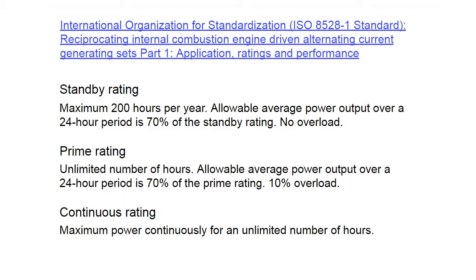As far as the different ratings, I saw some questions about different ratings of systems. So the ISO has ratings and performance requirements. Basically, a standby engine, by their standards, is a maximum of 200 hours a year. The allowable average output over a 24-hour period is 70% of its rating, and it does not have overload. So with a data center, where you'll see engines that may have to run for weeks because it's trying to maintain the system during the whole outage, that 70% rating can be an issue, so you might need to derate the engine.